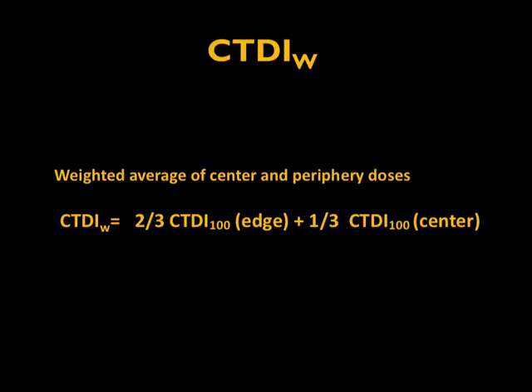Because of this, the physicist introduced another term called CTDI weighted, which is a measurement on the phantom taking two-thirds of the value at the edges and one-third of the value at the center, to arrive at what is called CTDI weighted.